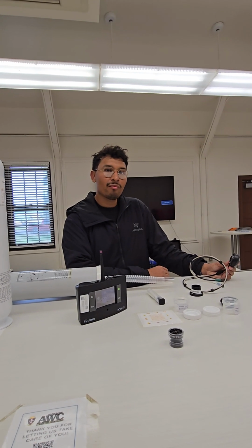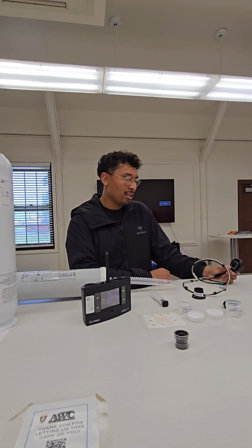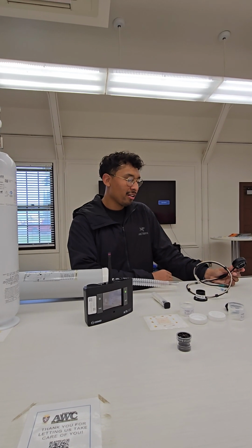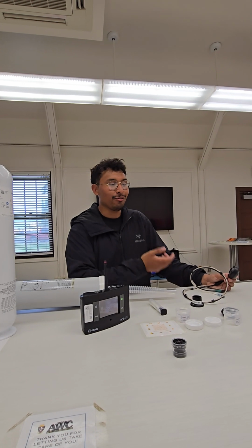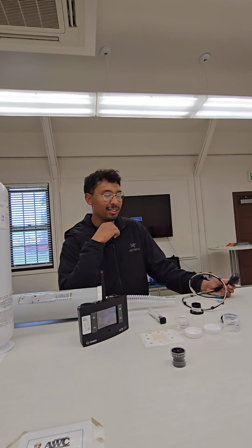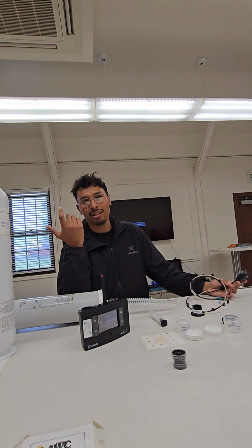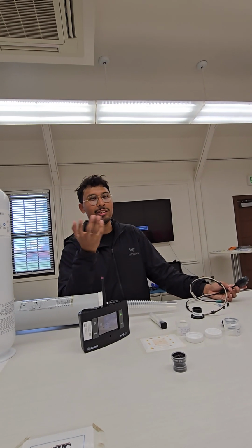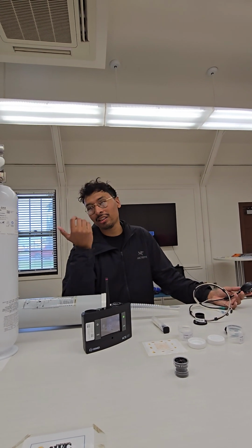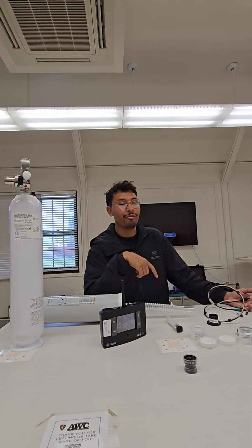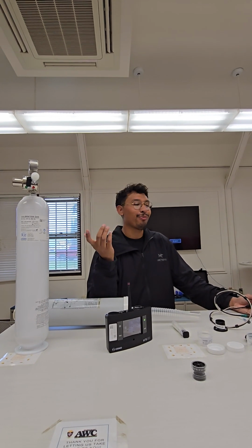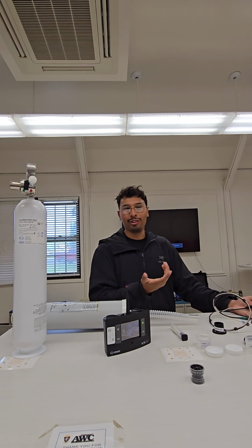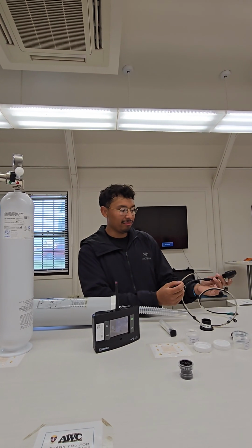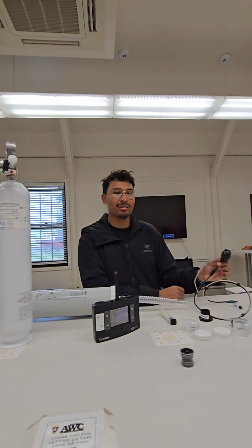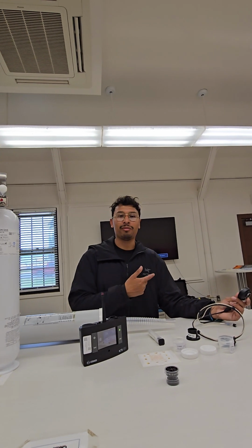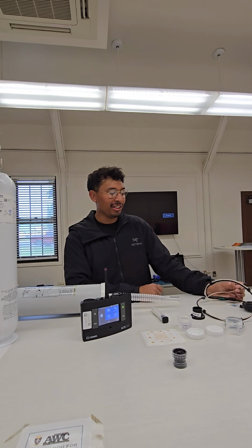What's the margin of error for an expired sampling line? How does it impact the tests? Basically, you're not getting accurate readings of what someone is producing, so like the CO2 expired or O2 inspired. So you wouldn't be getting accurate readings for the subject, is basically all it is. And also technically for the calibration, you'd probably fail it, indicating that you probably shouldn't run a test on the person because then the information wouldn't be correct. So you want to make sure that you do get new sample lines before you start running the test. It's just because you wouldn't be getting good samples from the subject. That's why you do need a new sampling line.